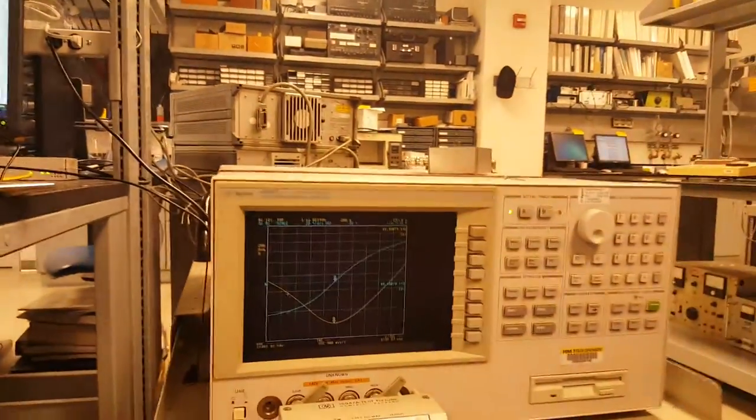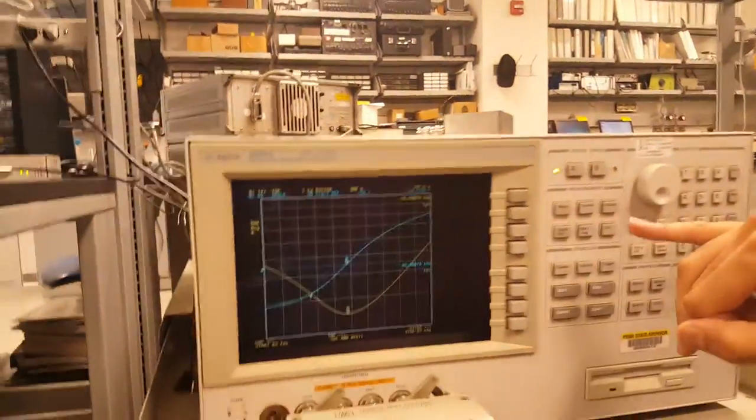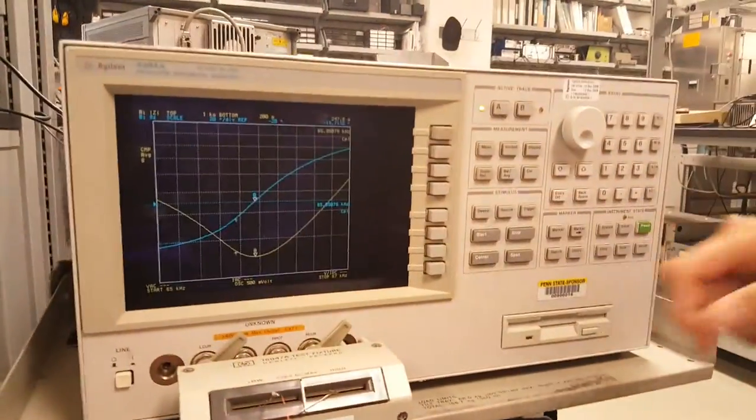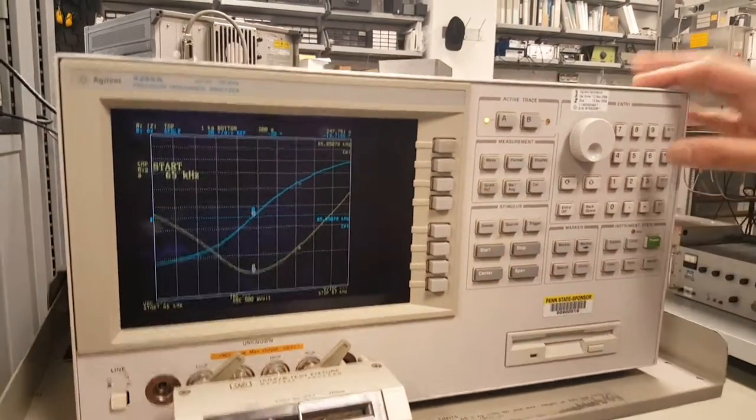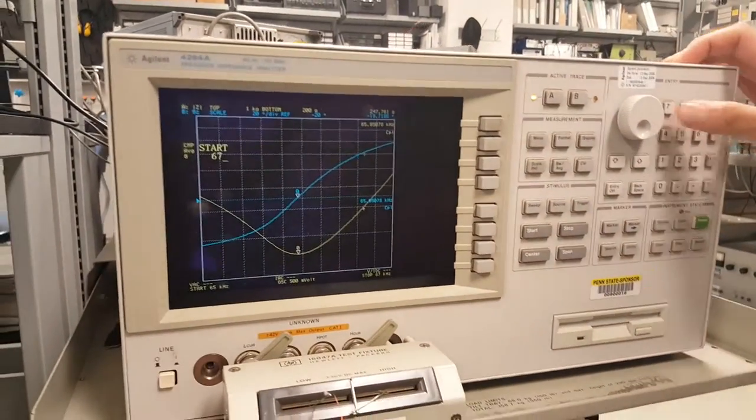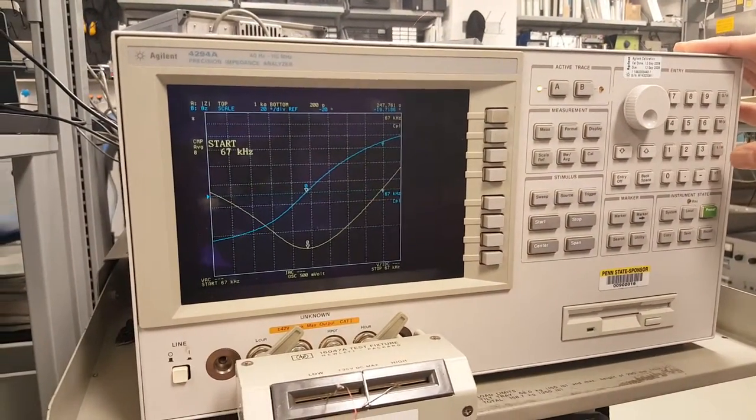So all your impedance data and phase data for this. So this is a very nice picture of resonance. Alright, so now we'll go to the anti-resonance point. The anti-resonance point, let's say, is around 67. So we start at 67 kHz.